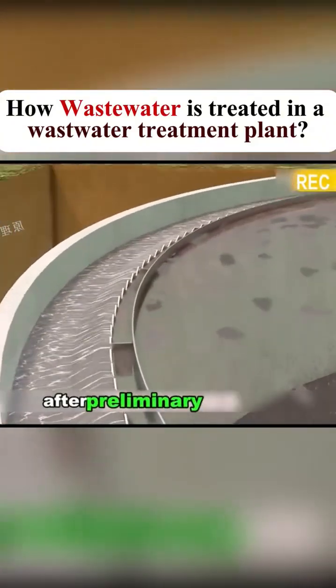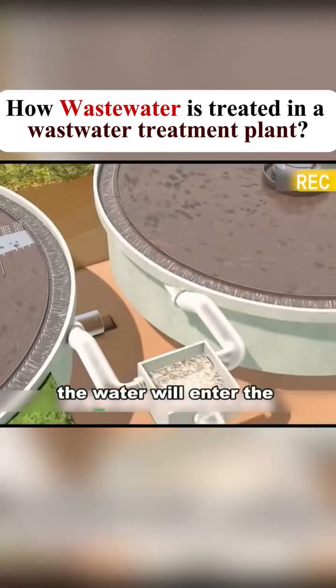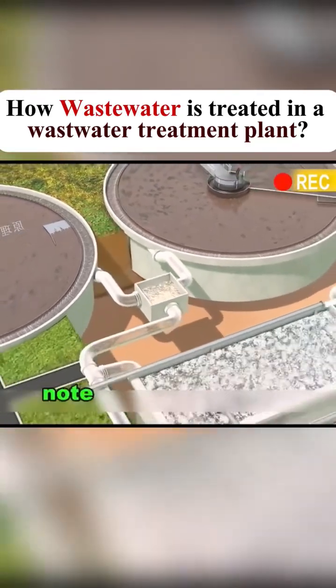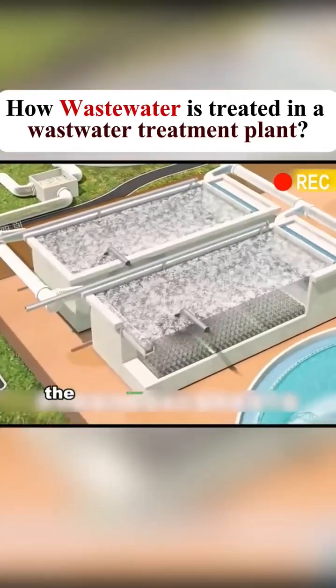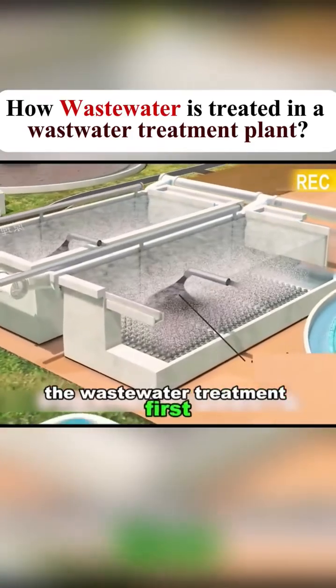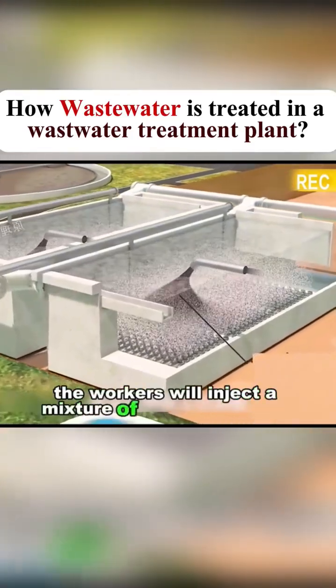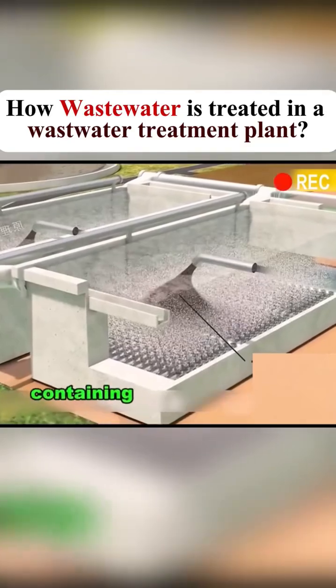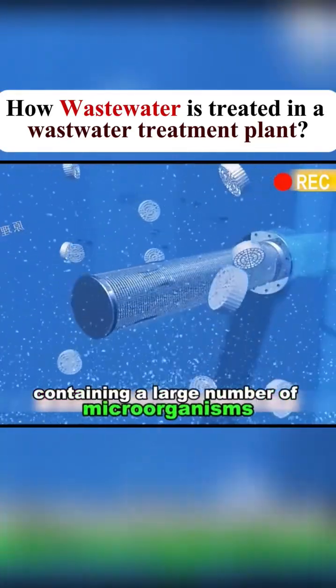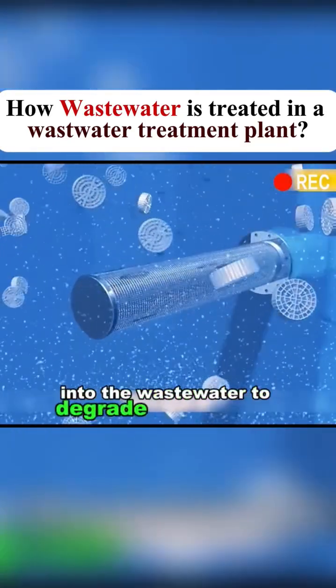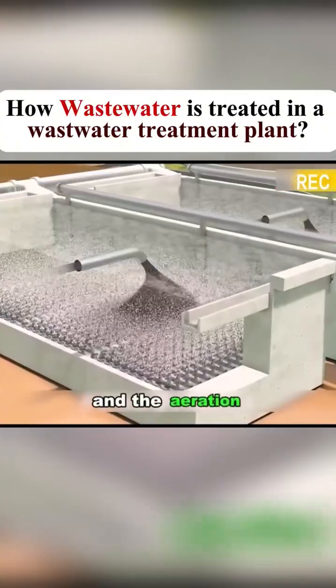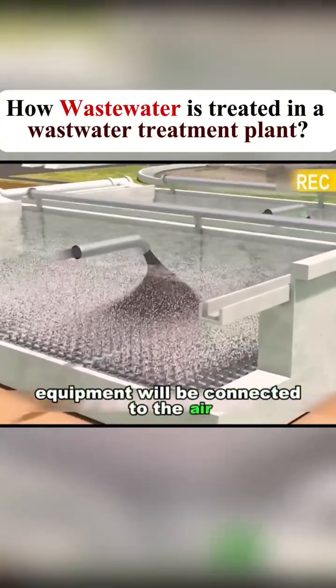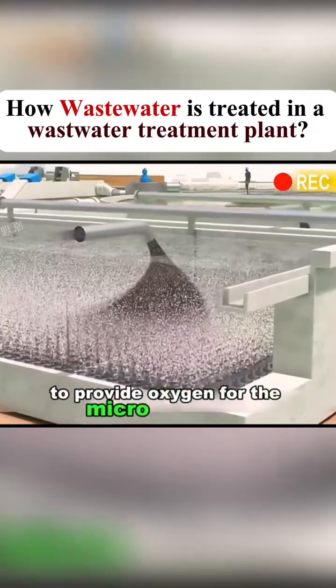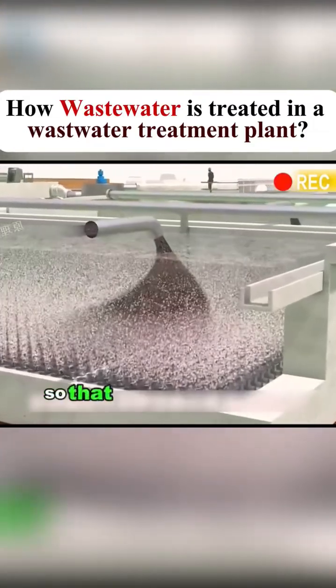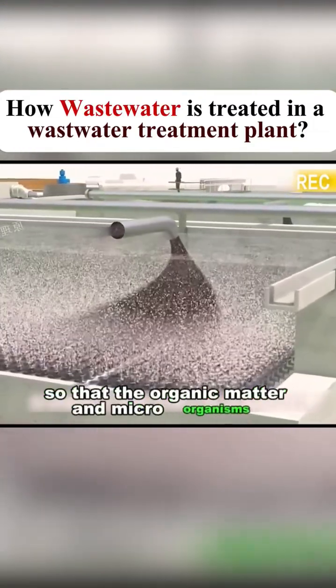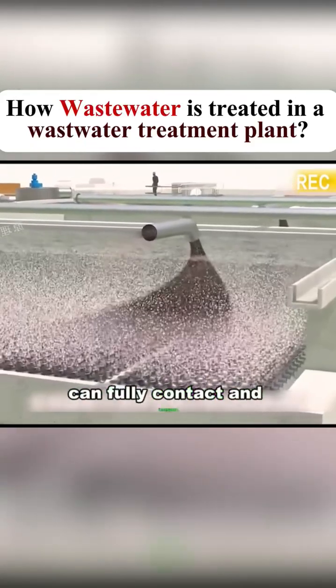The top layer of supernatant will be discharged through the archway. After preliminary treatment, the water will enter the biological treatment unit. Note that this step is the key part of the wastewater treatment. First, the workers will inject a mixture of activated sludge containing a large number of microorganisms into the wastewater to degrade the impurities. And the aeration equipment will be connected to the air to provide oxygen for the microorganisms, so that the organic matter and microorganisms can fully contact and integrate.